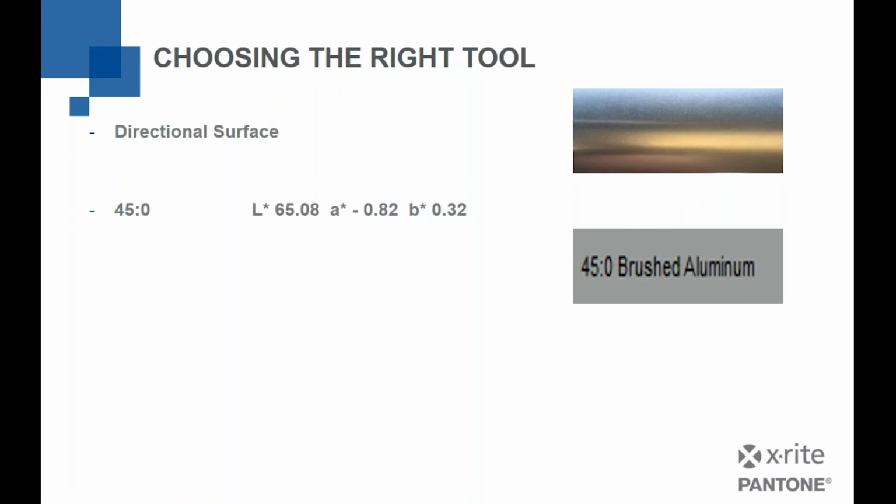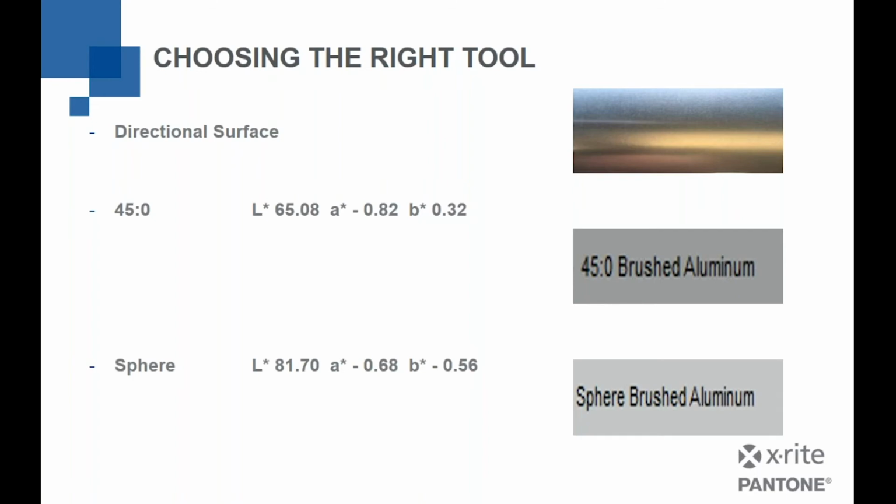It can't see the variation in the color. Of course, it sees it as a solid gray. And again, A and B, it's really, really neutral. And 65 is a pretty decent lightness value. So we would probably be very happy to take that instrument, compare multiple things, and get a repeatable measurement that agrees with human vision.